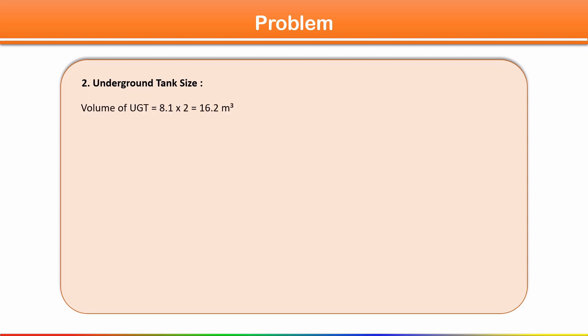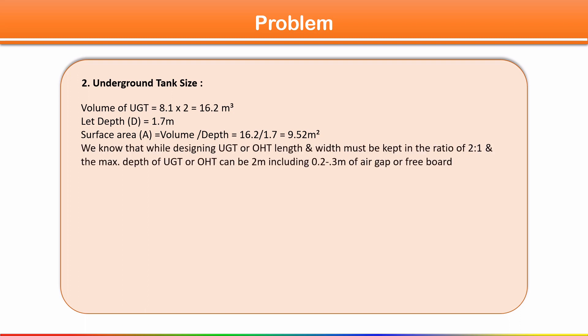For the underground tank, it must be designed for 2 to 3 days storage capacity. Designing for 2 days: volume = 8.1 × 2 = 16.2 cubic meters. Assuming depth of 1.7 meters (maximum 2 m including freeboard), surface area = 16.2 ÷ 1.7 = 9.52 square meters.